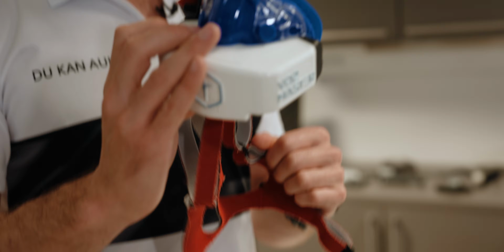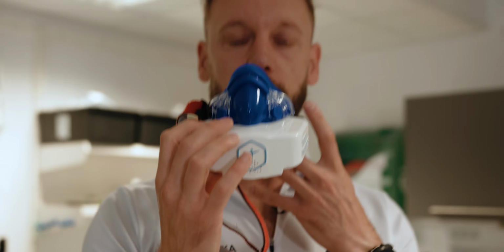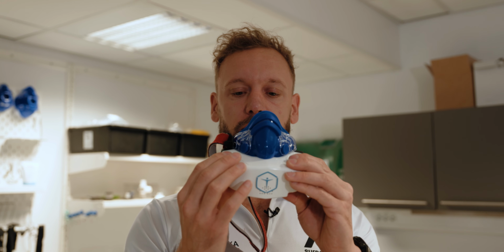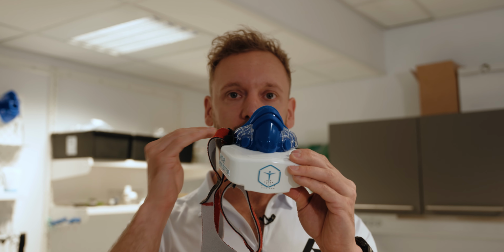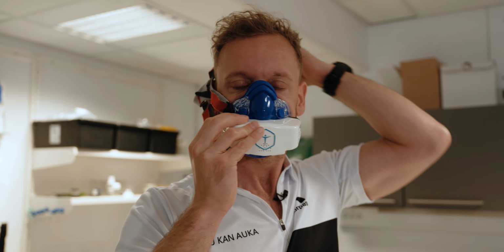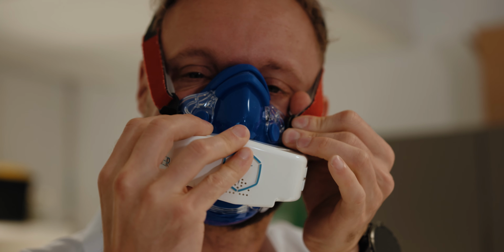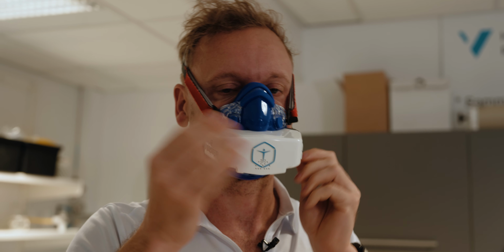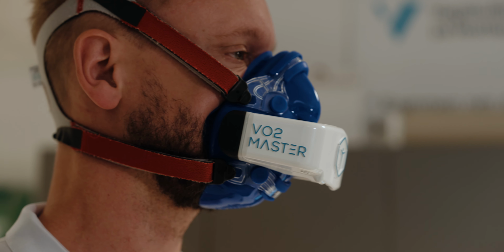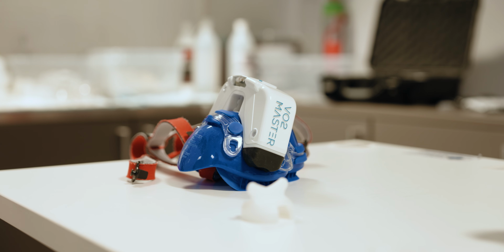So now I'm ready to put the mask on. When I put it on, I make sure that it's sealed all the way around and that the analyzer is level and centered on my face. The instrument was at room temperature when we calibrated. Now once you start to warm up, the instrument will gradually heat up, and at that point it's important to recalibrate to ensure that you get correct values.